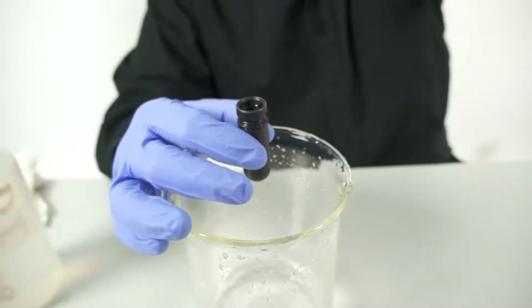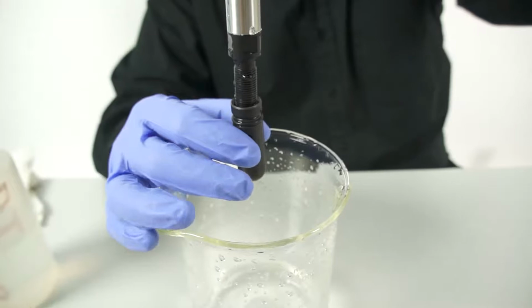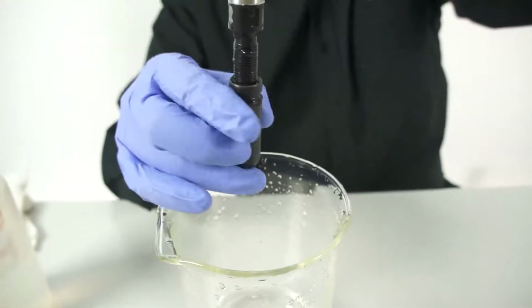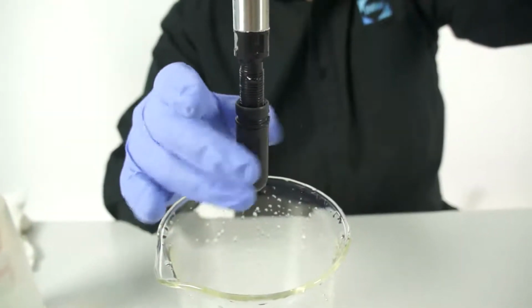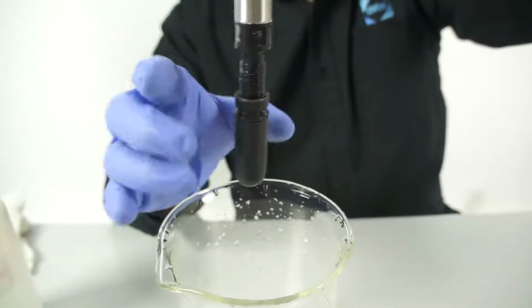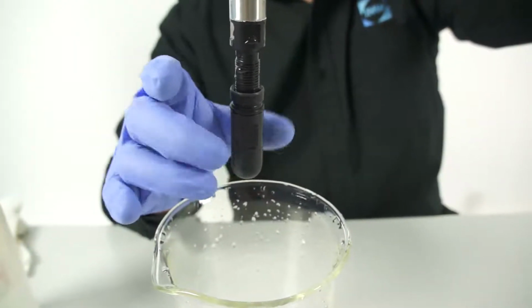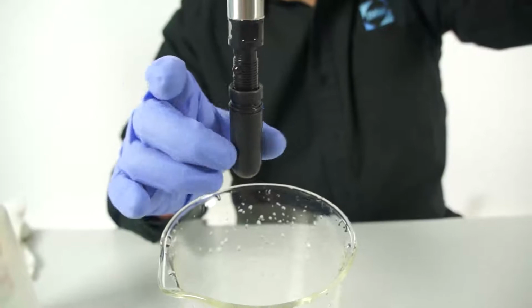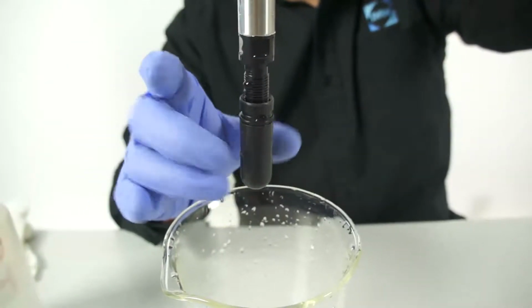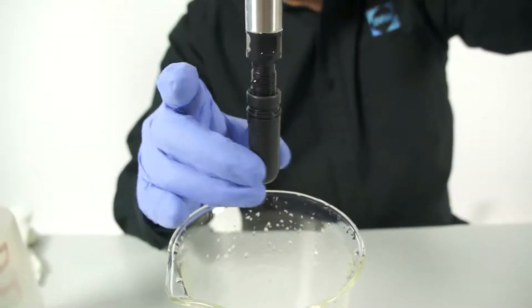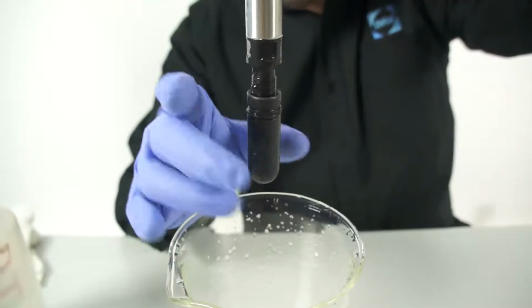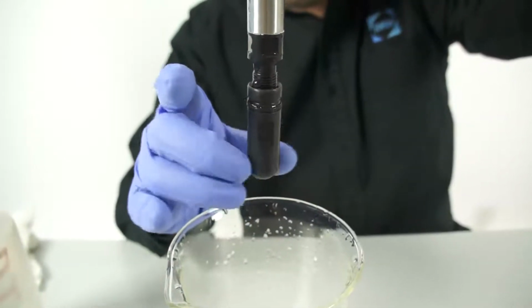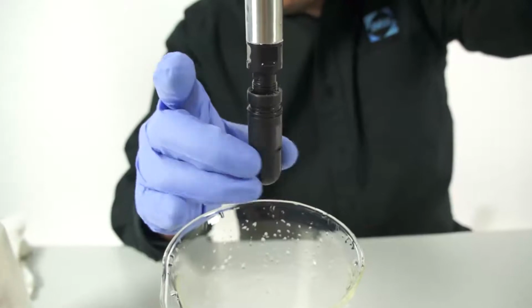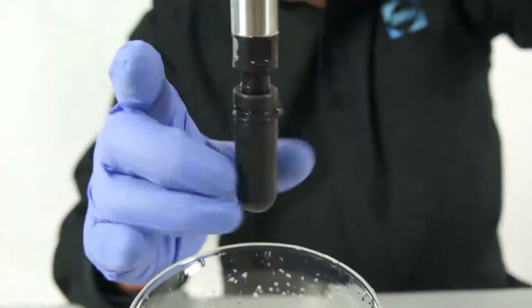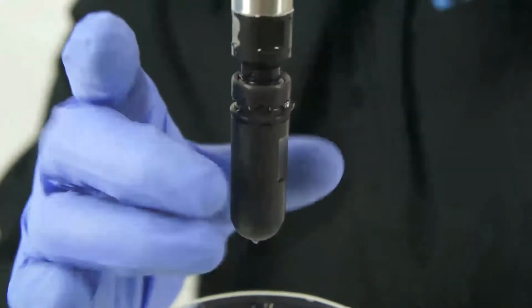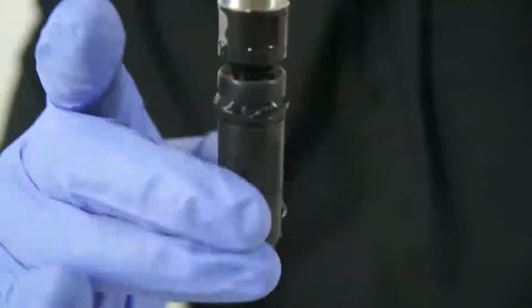And again, taking care to not damage that reference electrode, we'll gently thread the cap back on the probe. Tap gently to remove any air bubbles, as an air bubble trapped in the capillary can cause drift. And once you see the reference start to ooze out of the liquid junction ports, thread the reference cap all the way flush. Use care not to over tighten the cap, as this can damage the threads.